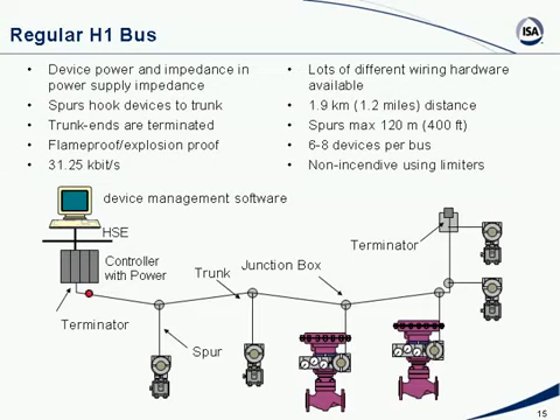The main wire going from the control room into the field is called the trunk. It is the one I'm illustrating here with the laser beam. Then off the trunk, we have spurs branching out to each individual device. These spurs can be up to 120 meters long, or 400 feet. Again, this is fairly unique to field bus, and it makes it very easy to connect these devices in the field. Also note that the trunk is terminated at each end. There's a terminator in the field, and there is a terminator at the control room end, so two terminators on a bus.